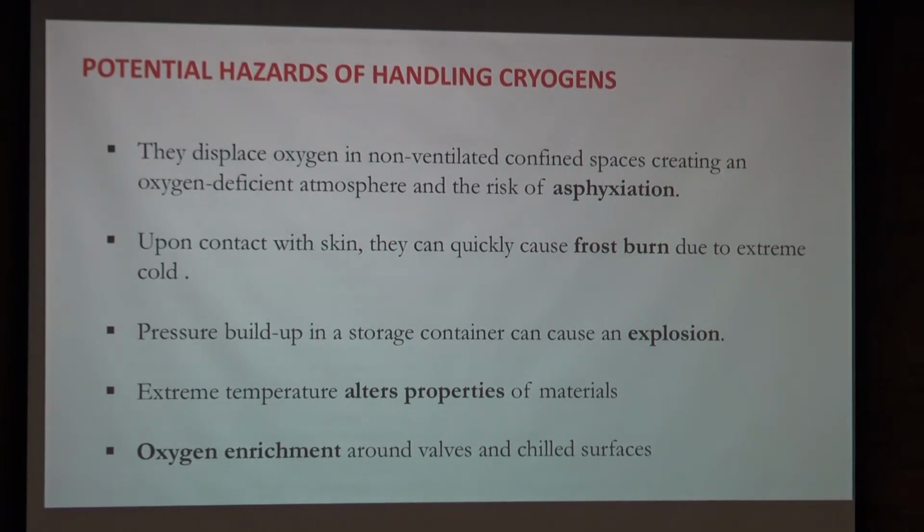When there is liquid evaporating, expanding into gas, and this gas cannot escape, then at some point you get into the regime where you run the risk that this vessel is actually exploding. Some of you may remember the Halloween dewar we had a couple of years ago, where the building had to be evacuated due to a helium dewar that had a blocked exhaust.